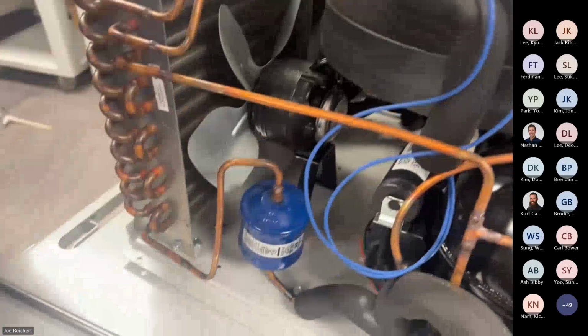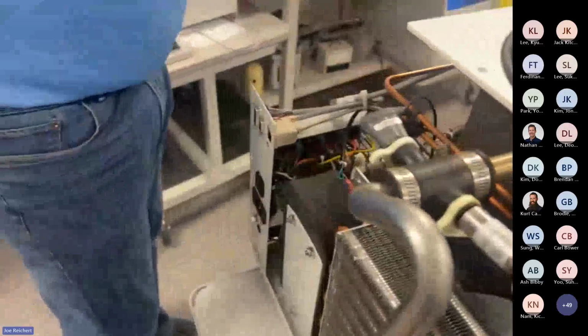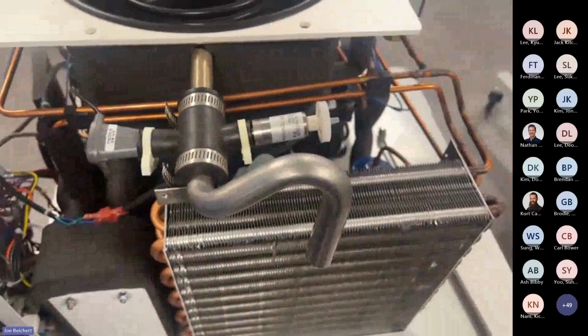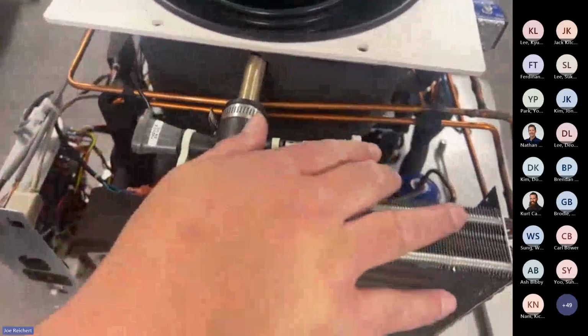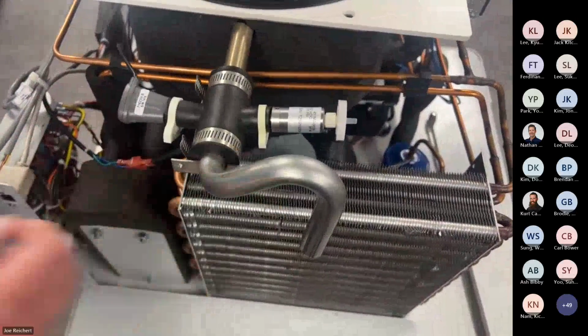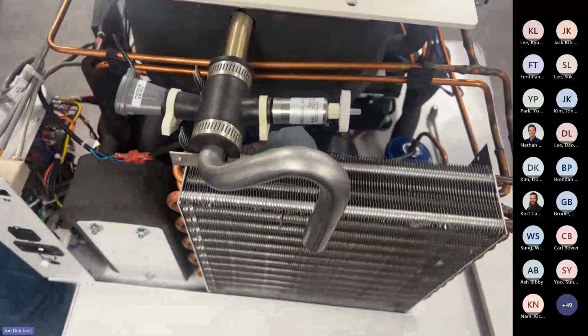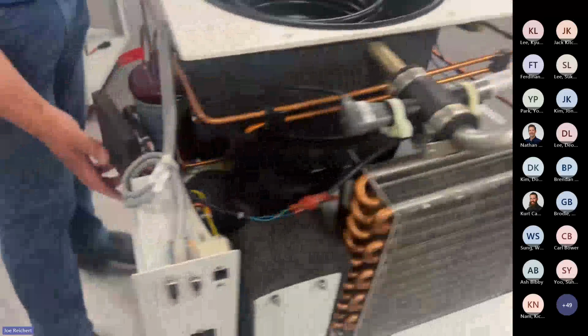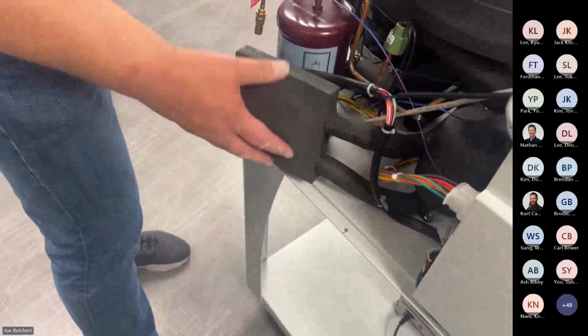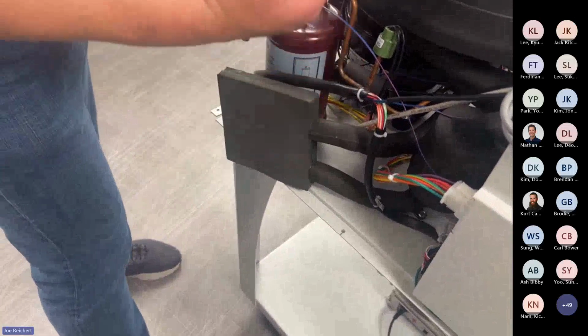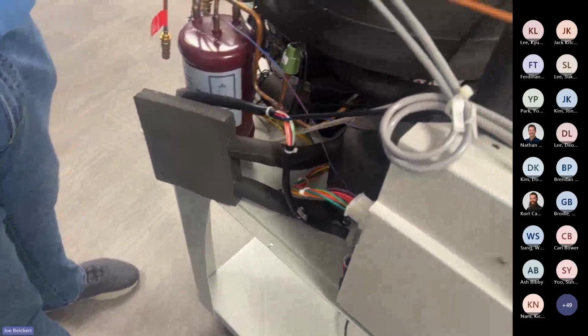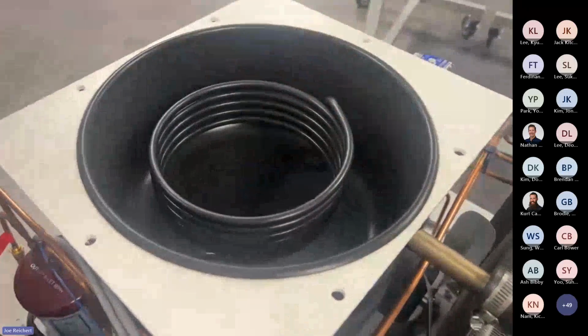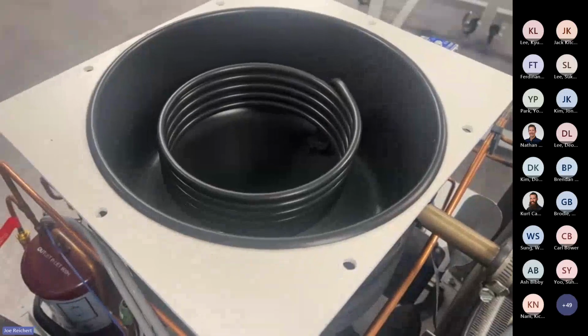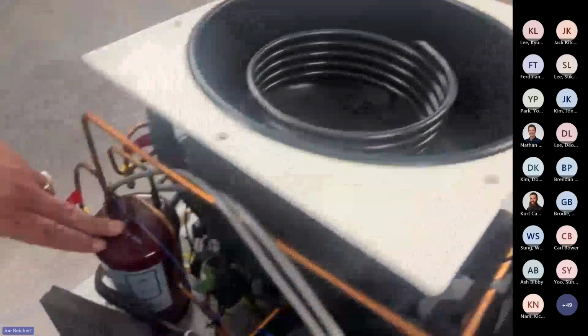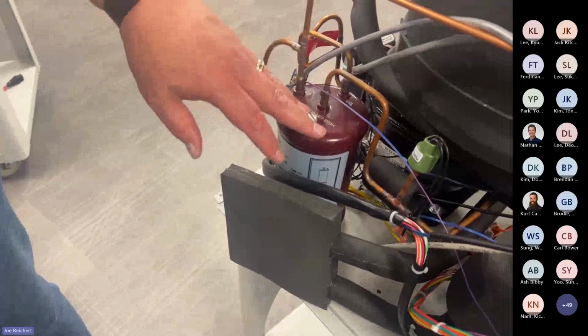Filter dryers, and this is a good look at the 4-port piece that I was using earlier for the vacuum troubleshooting. It has the vacuum release valve, vacuum sensor, and the back port on there for your vacuum hose. On the side here, this is your cap tube assembly. Inside this insulation it goes up through the coil, and it actually ends right about here on top of the coil inside. That's where the coldest point of the system is, right where that enters into there. And then an oil separator. This unit is a few years old to have the bigger oil separator.